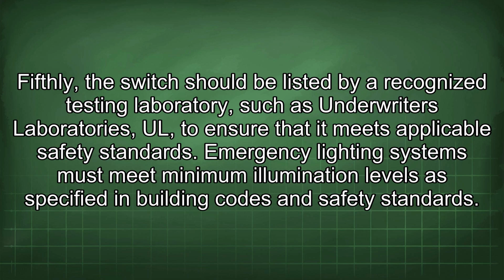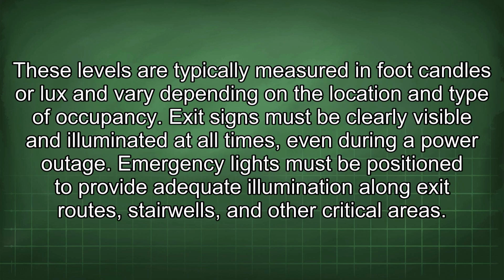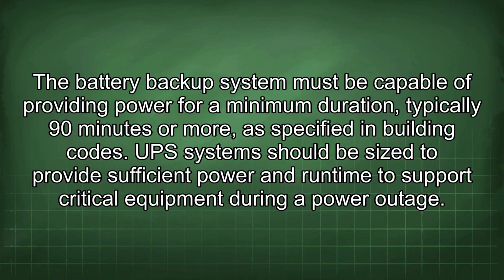Emergency lighting systems must meet minimum illumination levels as specified in building codes and safety standards. These levels are typically measured in foot candles or lux and vary depending on the location and type of occupancy. Exit signs must be clearly visible and illuminated at all times, even during a power outage. Emergency lights must be positioned to provide adequate illumination along exit routes, stairwells, and other critical areas. The battery backup system must be capable of providing power for a minimum duration, typically 90 minutes or more, as specified in building codes.